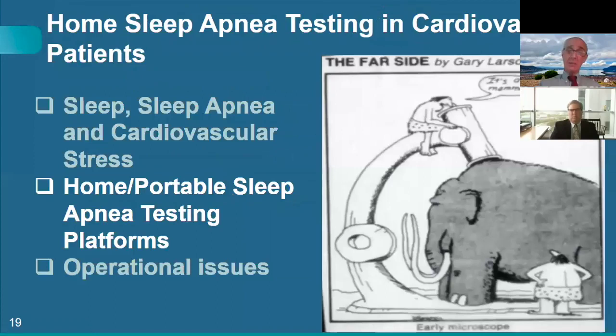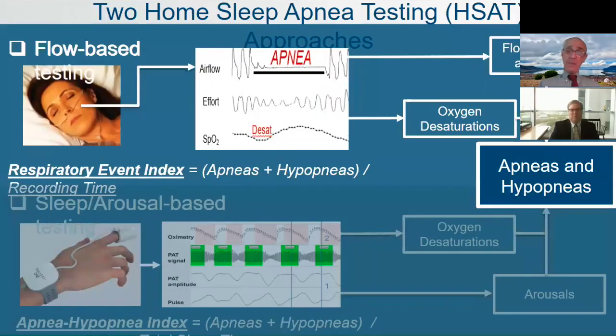Let's look at the flow-based testing platforms. These invariably encompass some sort of nasal pressure or airflow signal, a cannula that gives us a tidal airflow signal, a respiratory effort sensor of some type or another, and oximetry. From the flow, we derive an amplitude and shape of the flow waveform that gives us an idea as to when patients are having apneas or hypopneas. And it's based on these flow shape parameters that we can also figure out whether patients are having obstructive or central apneic episodes. We complement this information with dips in oxygenation, which are characteristic of sleep disordered breathing profiles, and from the combination of flow amplitude and shape and oximetry, we derive or count the number of apneas and hypopneas.